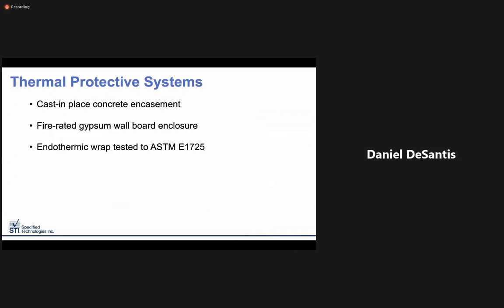Thermally protective systems are passive in nature, meaning they live inside the building, require little or no maintenance when properly installed, and should maintain their integrity for the life of the building. Traditionally, we've seen this accomplished in 3 ways. Cast-in-place concrete encasement, where the electrical pathway is completely immersed in thick concrete to prevent the heat of a building fire from interfering with the circuit's operation, as well as a fire-rated gypsum wallboard assembly, commonly referred to as a drywall shaft enclosure.